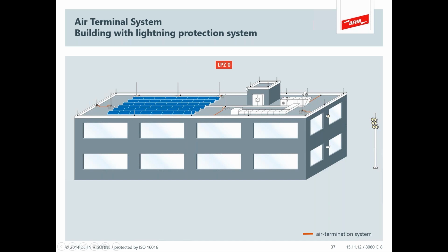Now, keep in mind, when we talk more about equipotential bonding, all the metal things that are up here are doing something. Like this solar array has electrical ground. That's not lightning bond, but it's an electrical ground. And the motor that goes into this chiller, this air handler has a green wire, and that's electrically bonding for fault safety of the motor. But that doesn't mean put a lightning rod on it. Just because it has a green wire doesn't mean you want your lightning rod on it. So sometimes you separate from that electrical bond. That's what separation gives you. So even just talking about the first aspect, you see that you have to pay attention to all the aspects.